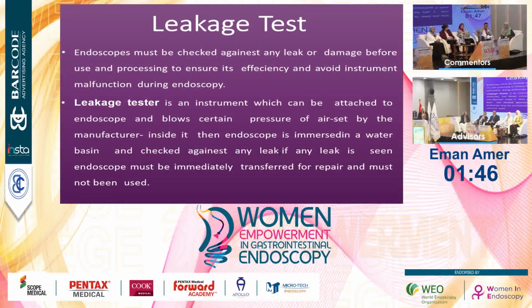So the leakage test. Endoscopes must be checked against any leak or damage before use and processing to ensure efficiency and avoid instrument malfunction during endoscopy. A leakage tester is an instrument which can be attached to the scope and blows air at a certain pressure, set by the manufacturer, inside it. Then the endoscope is immersed in a water basin and checked against any leak. If any leak is seen, the endoscope must be immediately transferred for repair and must not be used. Actually, if you use it and any leakage is there, the camera will be destroyed, and the camera is very expensive.